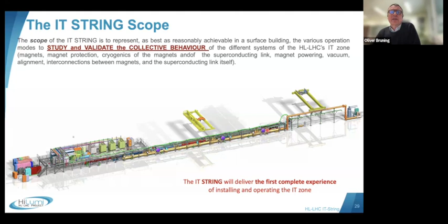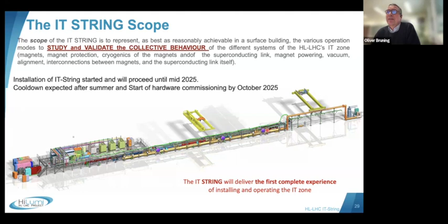So the installation is in full swing. Almost all magnets are there already. I think the last magnet will be installed next week, and then we start the interconnection of the magnets. We already started the pulling of the superconducting cable that makes the electrical connections of all the elements. And then in the second half of this year, the interconnection should be finished, and we plan the cool down of the string test. And then by the end of the year, we should start the first powering of the system. That will be really a major milestone for the project.